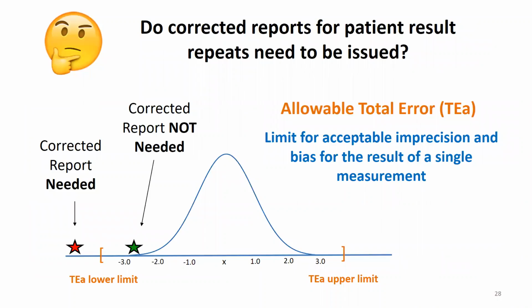So how do we know whether the error is significant enough to require corrected reports? If QC target means and SDs are set appropriately, QC should alert for events that are not yet clinically significant. That's the actual goal of an effective QC program, to catch errors before they adversely impact patient care. However, some events may indeed be clinically significant and corrected reports need to be issued.